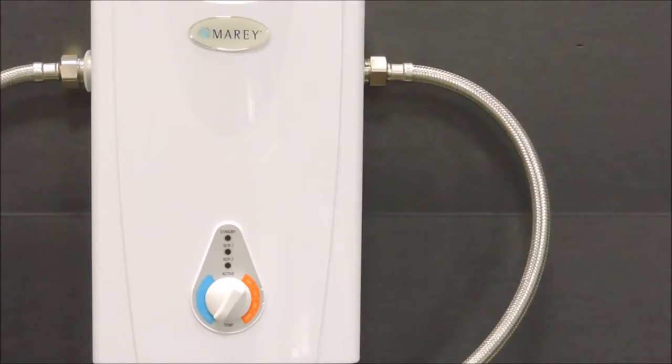Run water through the heater for a few minutes to purge all the air from the system. Shut it off at the faucet to pressurize the system. And at this point, check for and fix any leaks. If there are no leaks present, then let's move on to the next step.